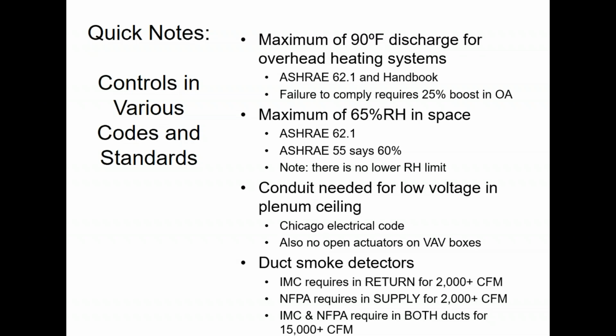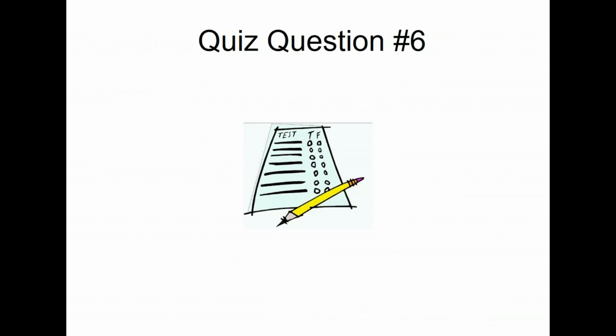And then for both of those codes, either one, if you're following either code, if you get to 15,000 CFM, you always require a supply and a return duct smoke detector. Sometimes these are provided by the controls guy, sometimes the mechanical, sometimes the electrical, but someone's got to provide them and wire them up. And then obviously they're wired to shut down the supply fans in the case of duct smoke detection so we don't spread the smoke around.